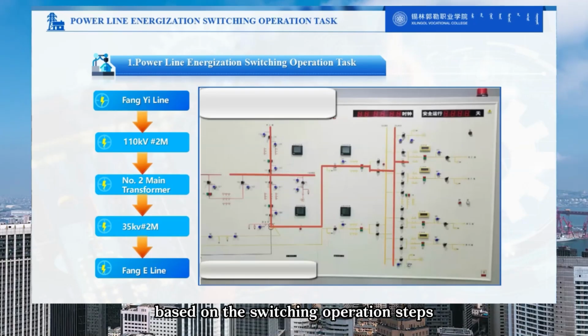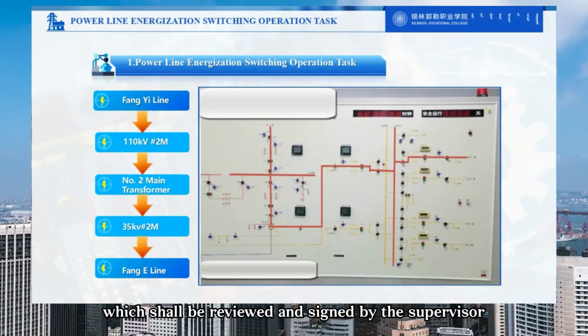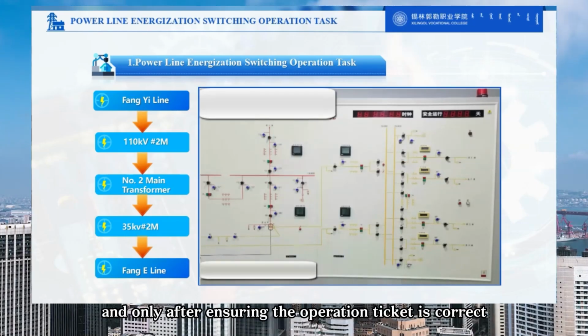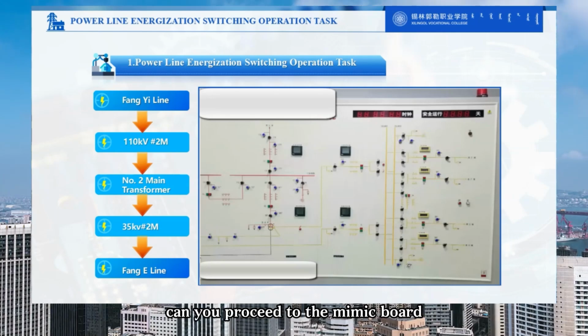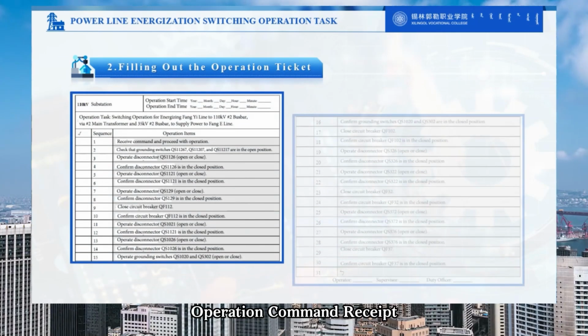Based on the switching operation steps, draft an accurate operation ticket, which shall be reviewed and signed by the supervisor. And only after ensuring the operation ticket is correct can you proceed to the MIMIC board for operation. Command received. Operation command received.